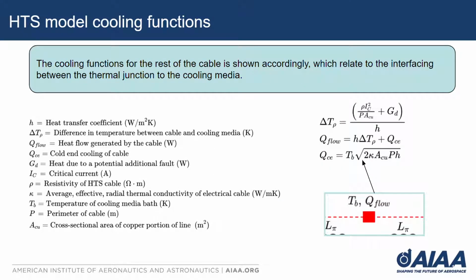Now that we have the heat transfer coefficient for both medias modeled, we can model the rest of the cooling functions. These relate to interfacing the thermal junction to the cooling media. So we have the difference in temperature between the cable and cooling media shown as a function of resistivity, the critical current of the line, the geometry of the line where P is the perimeter and A is the area of the copper portion, and heat generation due to a potential additional fault and the heat transfer coefficient.